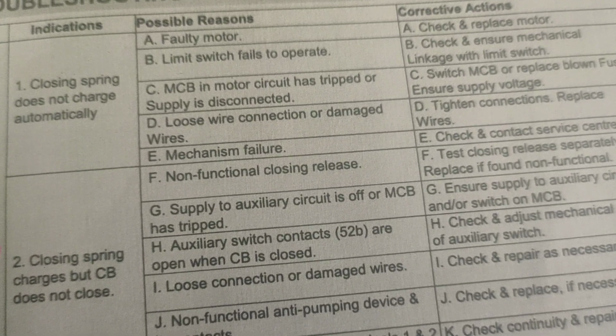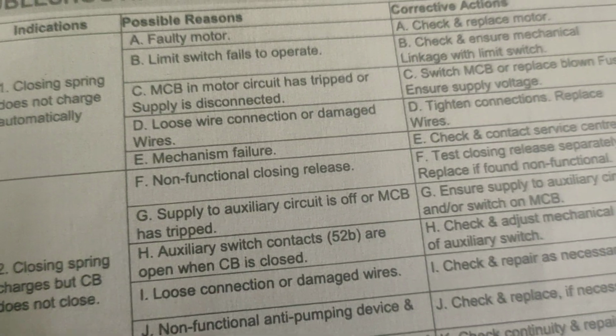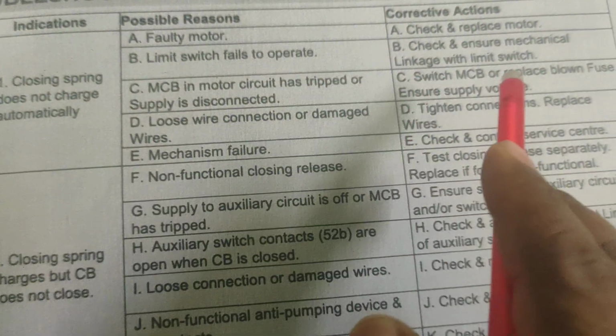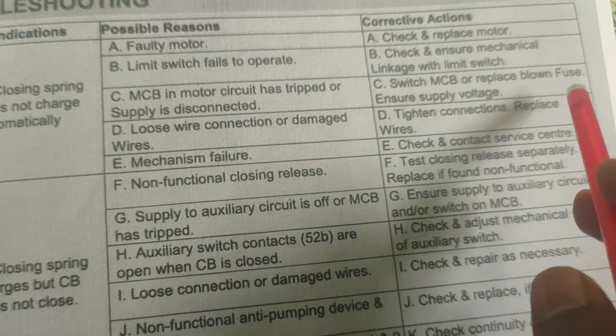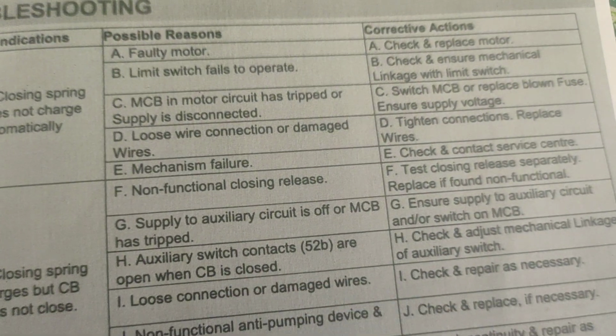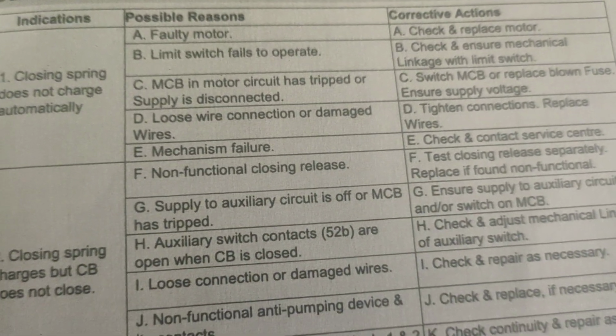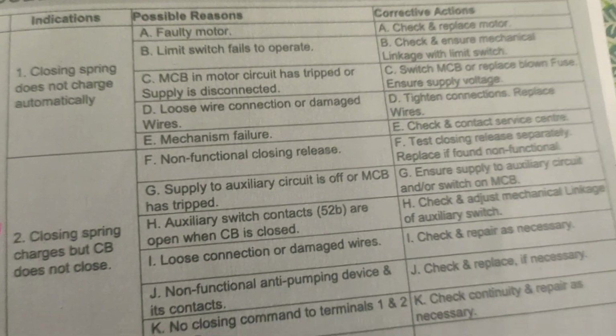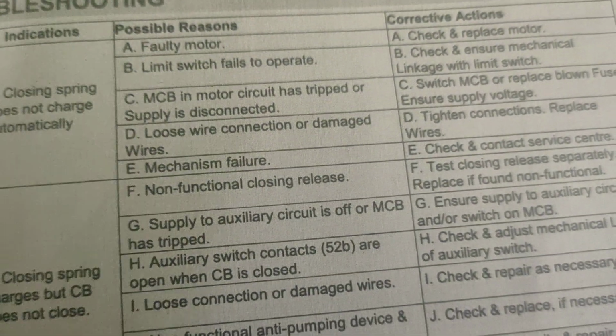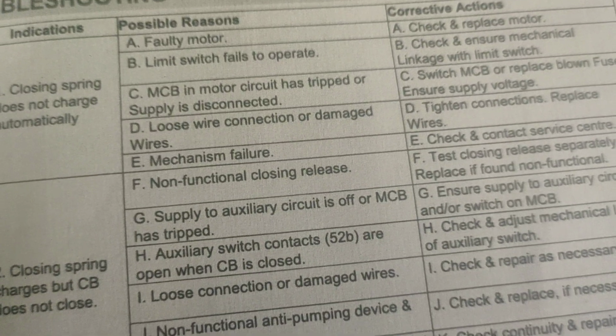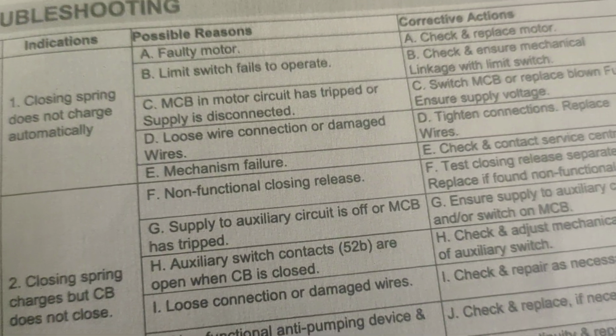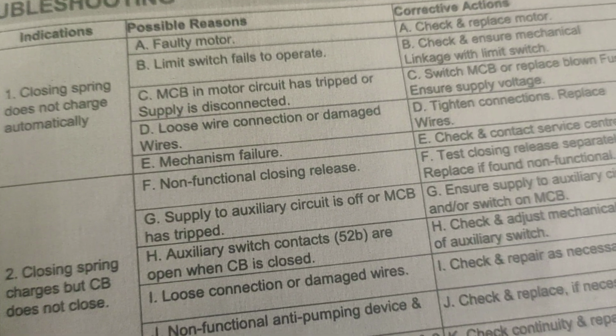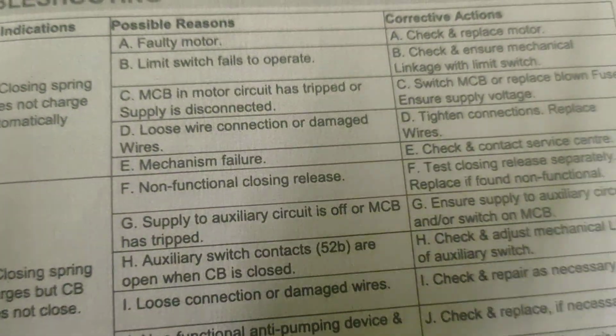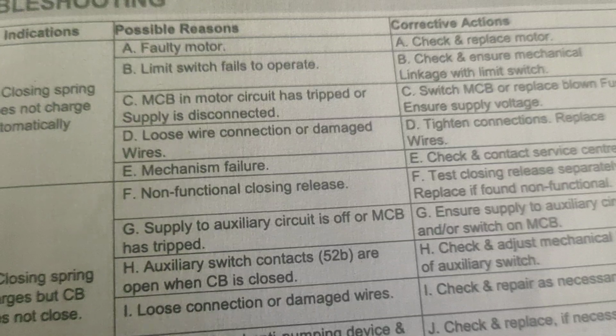So what will be the problem? The MCB may have tripped. If the MCB has tripped, the supply will be disconnected. Then switch on the MCB, replace the blown out fuse, and ensure the supply voltage. Blown out fuse means that in the motor circuit somewhere an MCB is present, somewhere a fuse is present. If a fuse is present, you just change it with a good fuse, and then the problem may be solved. Next, a loose wire connection or damaged wire: if any wire inside is burned out or there are loose connections, the voltage does not reach the motor and the motor does not operate, so the circuit breaker does not close. The problem can be overcome by tightening the connections and replacing the wire.